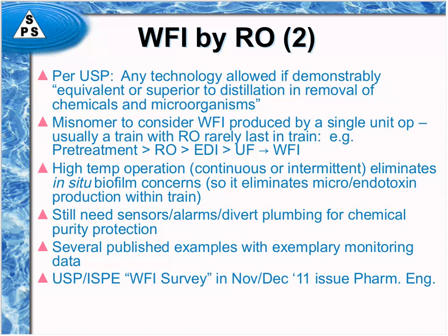And the bottom line is that there is a plethora of ways of producing water for injection that very well control the endotoxin and the microbial content of the water. And it's not just any one technology, it's any number of technologies and combinations of technologies that can work just as well and often more cheaply than the distillation process.